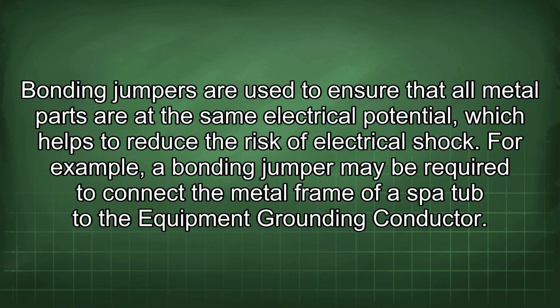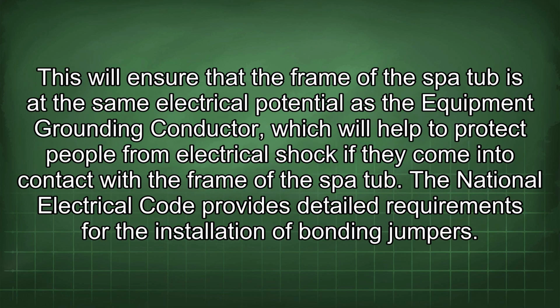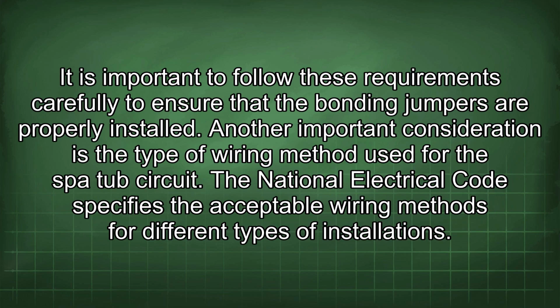For example, a bonding jumper may be required to connect the metal frame of a spa tub to the equipment grounding conductor. This will ensure that the frame of the spa tub is at the same electrical potential as the equipment grounding conductor, which will help to protect people from electrical shock if they come into contact with the frame of the spa tub. The National Electrical Code provides detailed requirements for the installation of bonding jumpers. It is important to follow these requirements carefully to ensure that the bonding jumpers are properly installed.